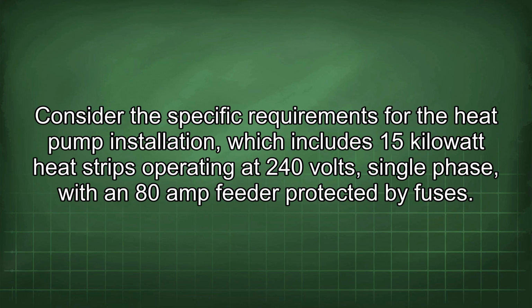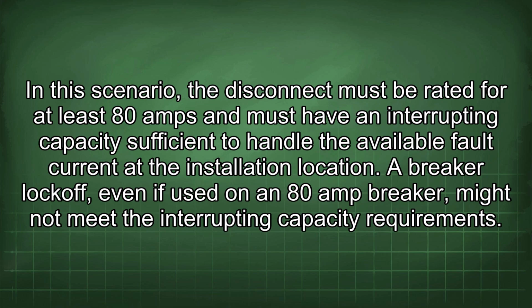Consider the specific requirements for the heat pump installation, which includes 15 kilowatt heat strips operating at 240 volts, single phase, with an 80 amp feeder protected by fuses. In this scenario, the disconnect must be rated for at least 80 amps and must have an interrupting capacity sufficient to handle the available fault current at the installation location. A breaker lockoff, even if used on an 80 amp breaker, might not meet the interrupting capacity requirements.